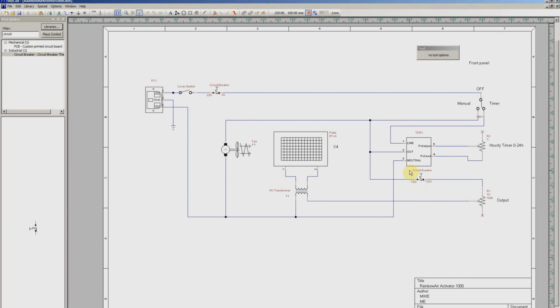Now, as I mentioned, this small circuit breaker, the half amp one, is basically in there to protect your high voltage transformer. So if you get a hard short across here, and not just the arcing over that I showed, it will trip this circuit breaker and protect your transformer. So that's the first thing, if this circuit breaker is tripping, you should look for is a hard short between these two bus bars. As far as I can tell, just a plate arcing through won't draw enough current to trip this.